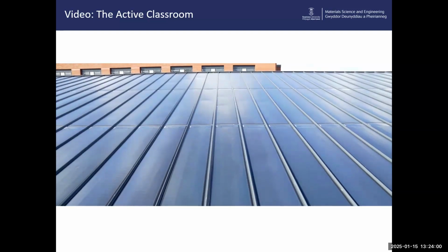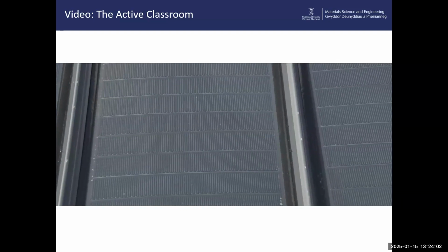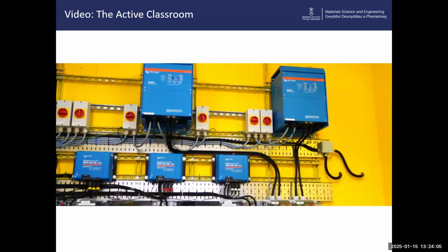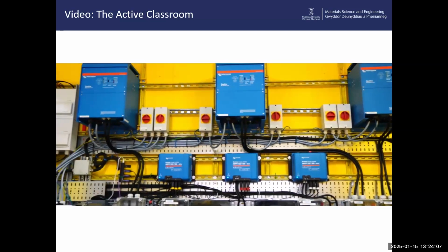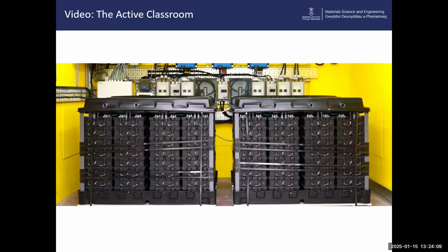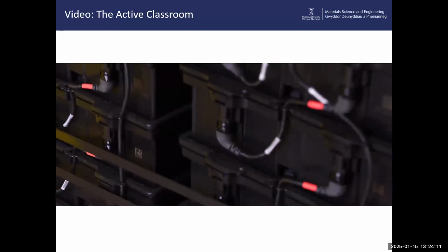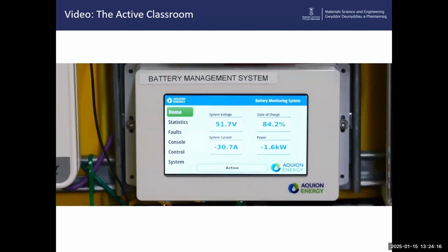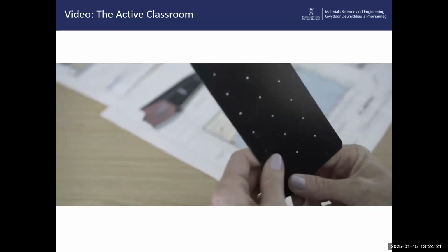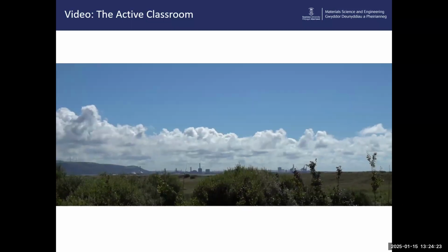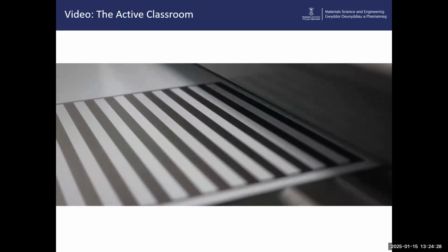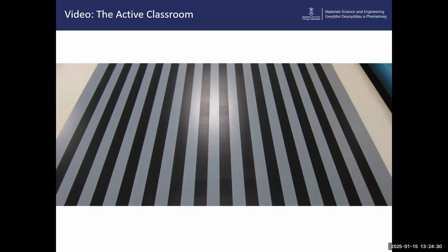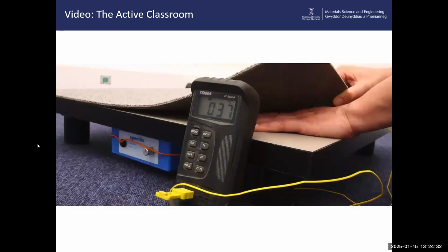The steel roof has 16.2 kilowatt peak of integrated photovoltaics. They are used to power the building directly and to charge 2 saltwater batteries. The batteries have a combined capacity of 40 kilowatt hours, enough to power the building for at least 2 days without top-up. Heating is provided by a solar thermal collector on the south-facing wall. Warm air is drawn into the building through the tiny perforations. On a sunny day, it can provide enough heat for the building even in the middle of winter. Heating is also provided by floor panels coated in an electrical resistive coating, which heats up when a low voltage is applied.